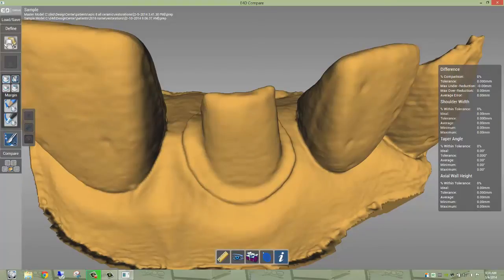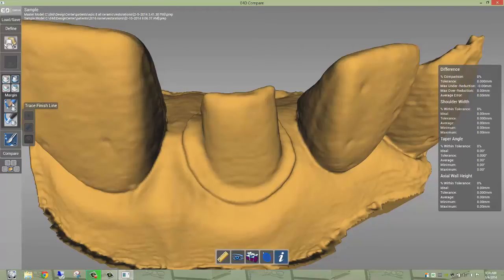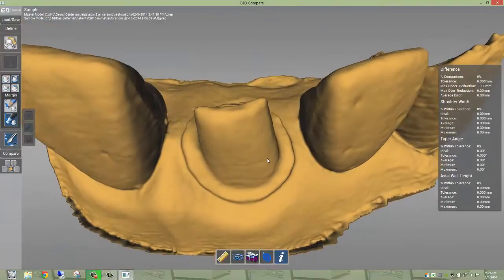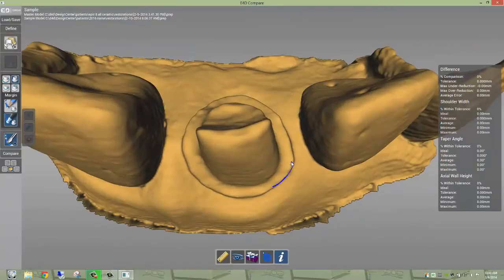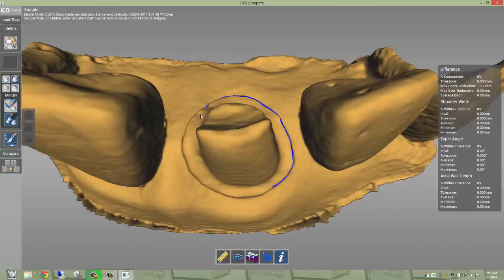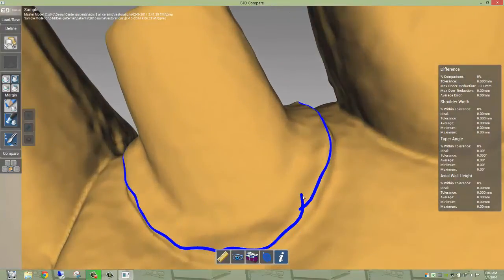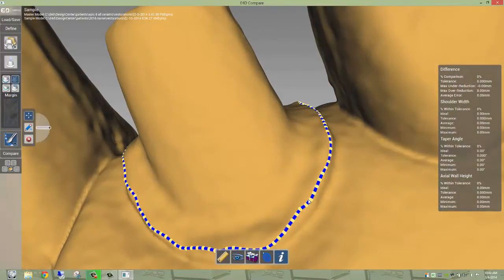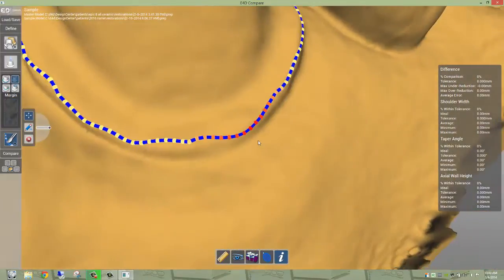We have Margin, which is your typical self-explanatory margin. We have Axial Base, which is the internal angle of your finish line, and we have Occlusal. So let's just go through these, and we're going to mark the margin right now. I'm going to use the Wand. We have two options, Tracer Wand, but for this one, let's just use Wand. And Wand is kind of automatic in that it finds the hard edge for you. And so you go a third of the way, and you click, and you just kind of click it in stages. And when you get back to the beginning here, you click it, and it's going to automatically seal that.